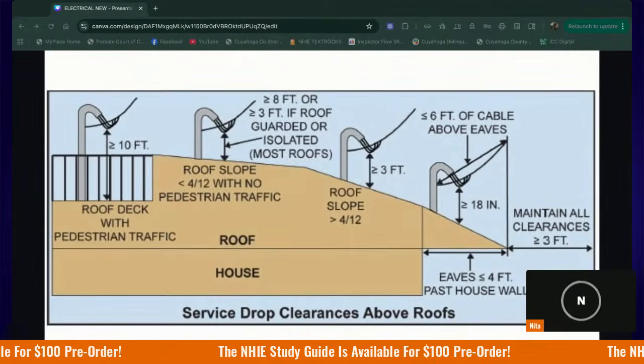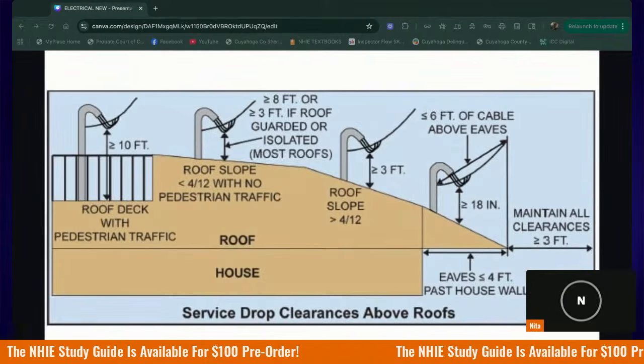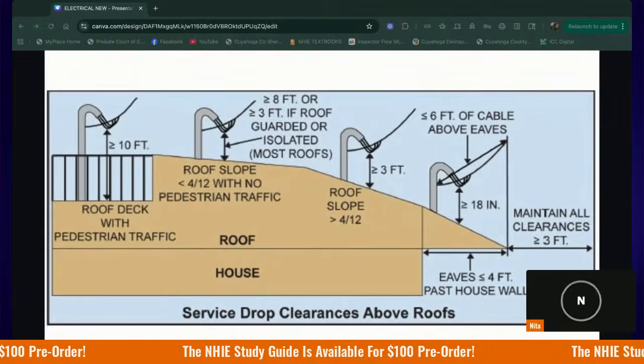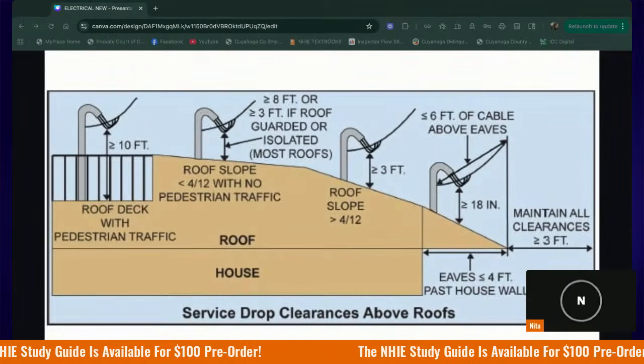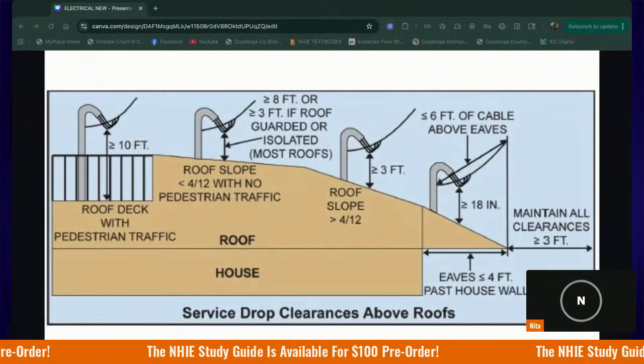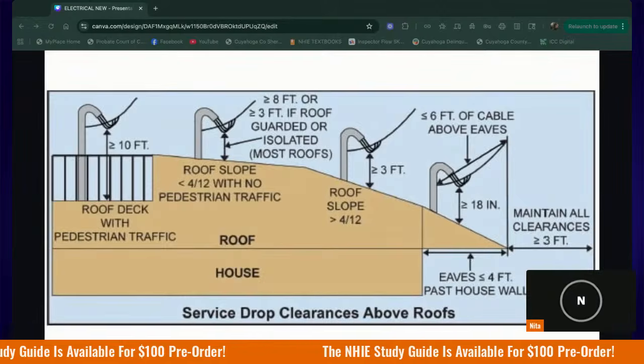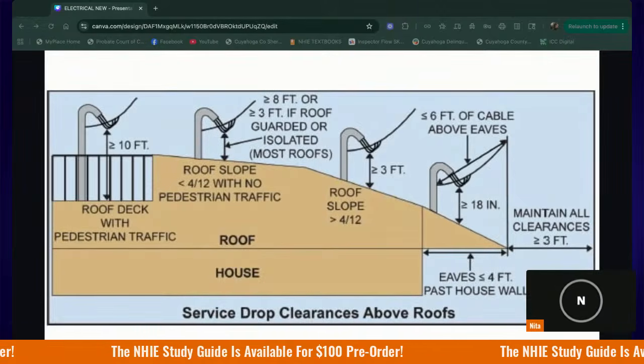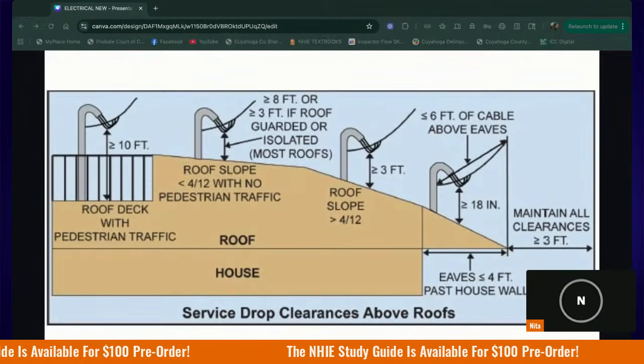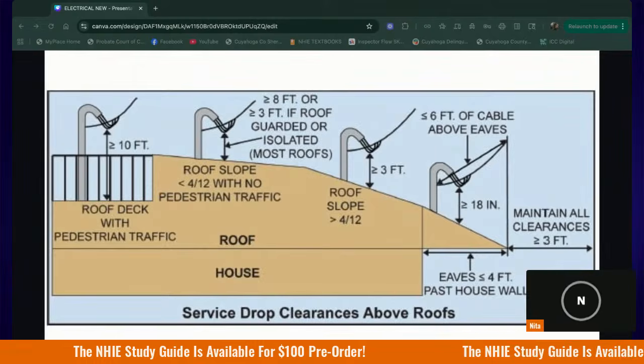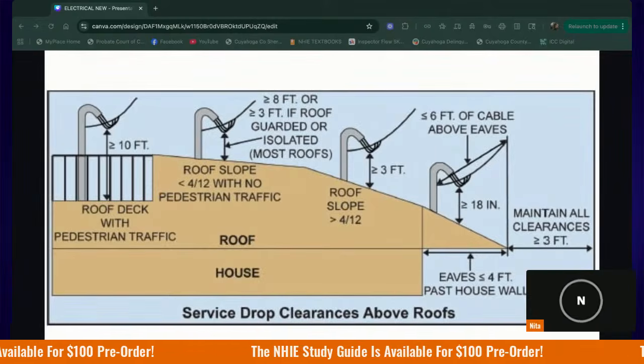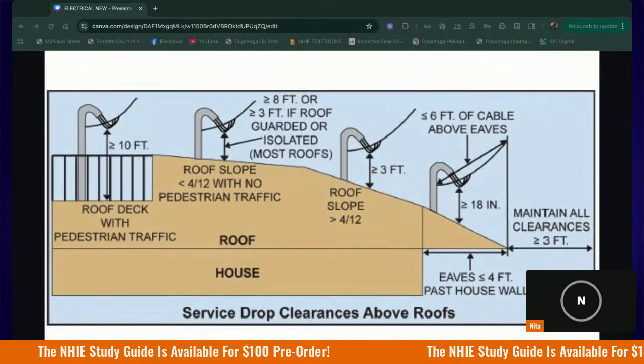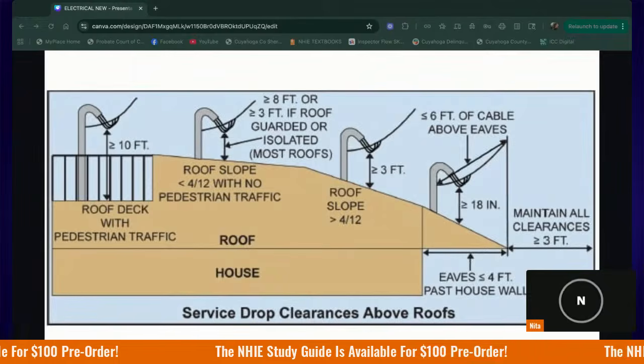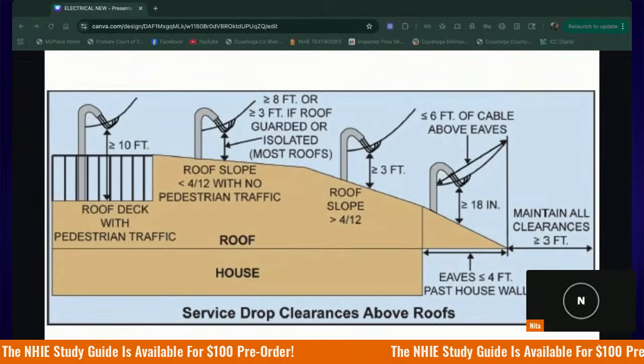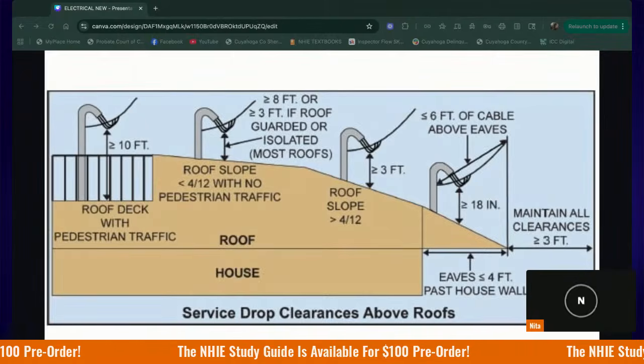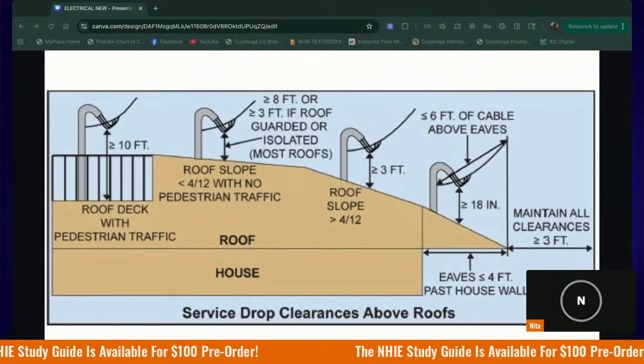We're inspecting it visually from the ground, because you are never going to attempt to actually touch the conductors directly. If the clearance appears borderline close, I would document it and recommend further evaluation. This is a very common defect on older homes that are in disrepair and have deferred maintenance. The lines will sag over time due to the weather, or just due to the age of the actual house. So again, a walkable roof deck, 10 feet; low slope roof, 8 feet; steep roof, 3 feet; and at the edges or the eaves, at least 18 inches.